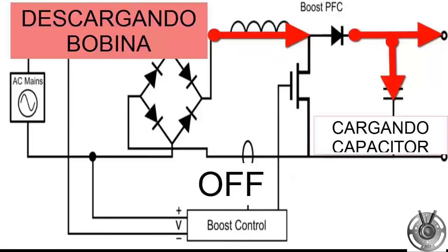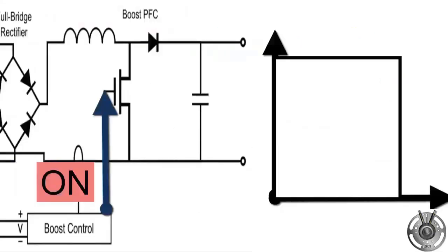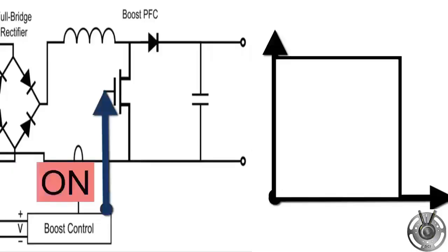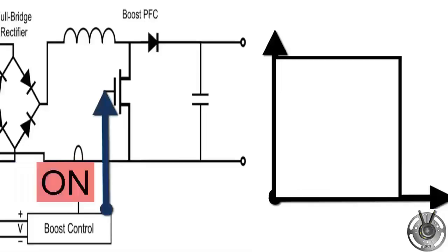At this point, we must remember that testing or diagnosing the reactor is very simple. You just need to disconnect the power supply to the reactor, and with a multimeter on the ohm scale, measure the electrical continuity of this component. If you have the equipment manual, measure its resistance and compare it to the value in the manual.